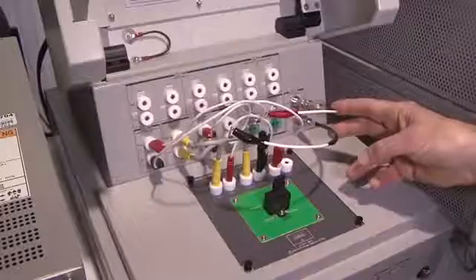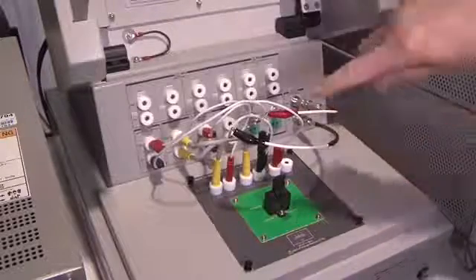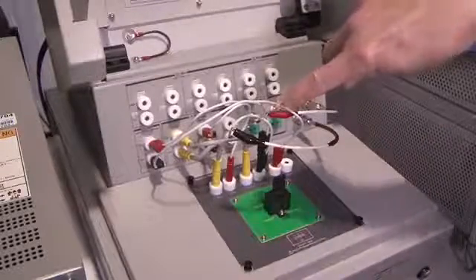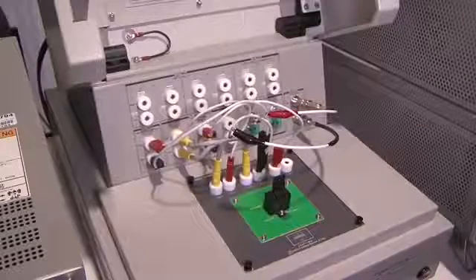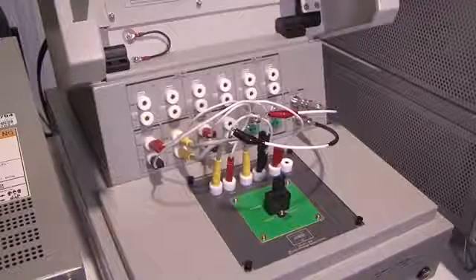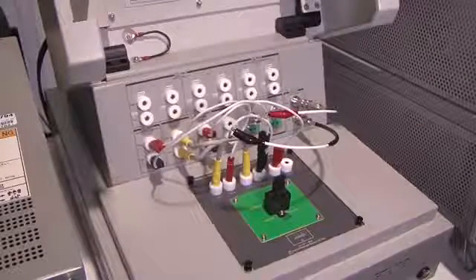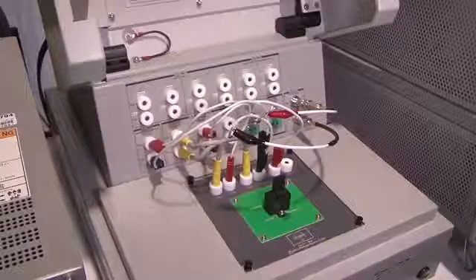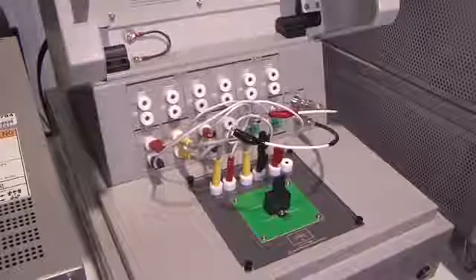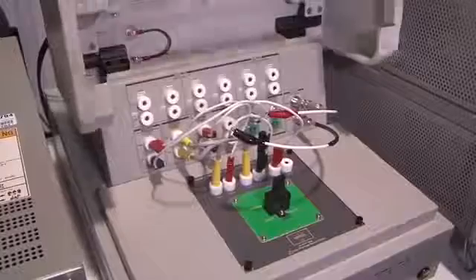So what we have here is our N1265A test fixture current amplifier. The current amplifier is actually built into this box. So this can actually go to 1500 amps. And as you can see, this is completely safe. So to actually do the measurement, I now have to go ahead and close the box.